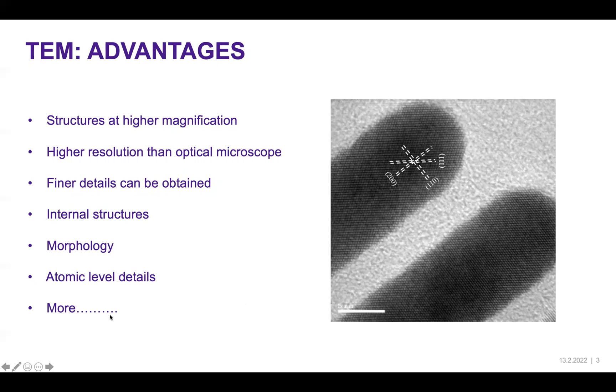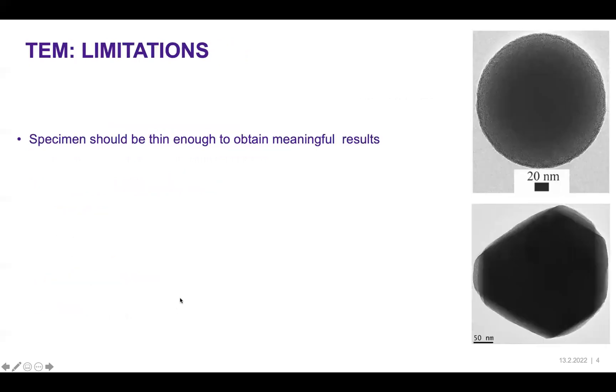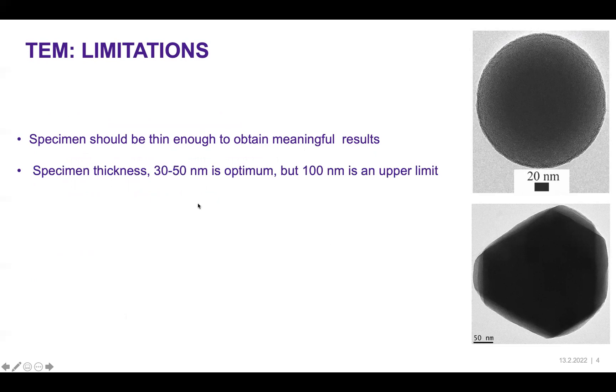We can see much more, such as the elemental composition of nanoparticles. However, there are limitations. One of them is that the sample should be thin enough to obtain meaningful results. Specimen thickness of about 30 to 50 nanometers is optimum, but 100 nanometers is the upper limit.